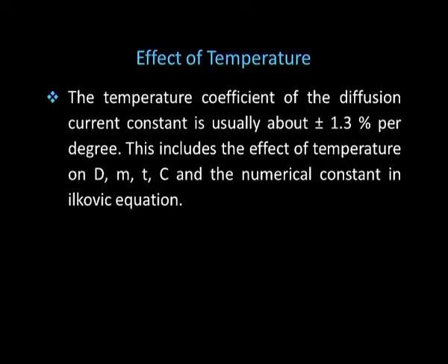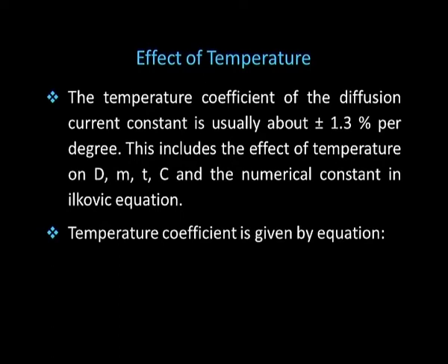Then effect of temperature. The temperature coefficient of the diffusion current constant is usually about plus minus 1.3% per degree, which includes the effect of temperature on diffusion coefficient, mass, drop time, concentration and the numerical constant in Ilkovic equation. Temperature coefficient is given by an equation.